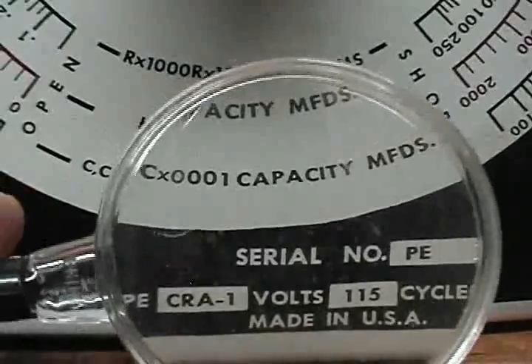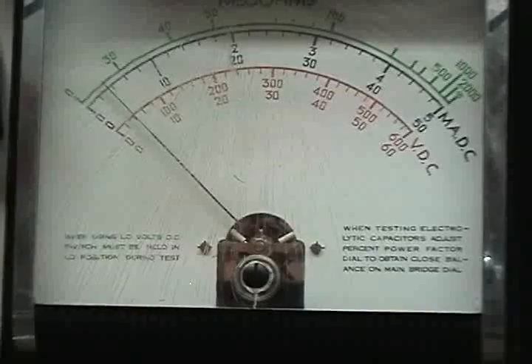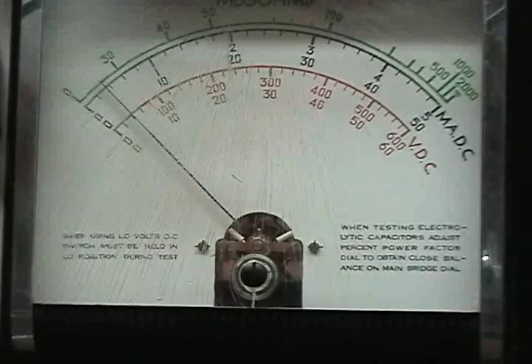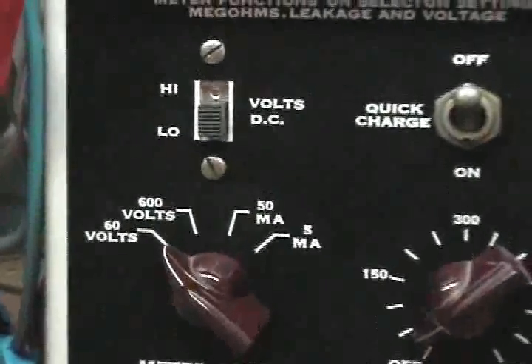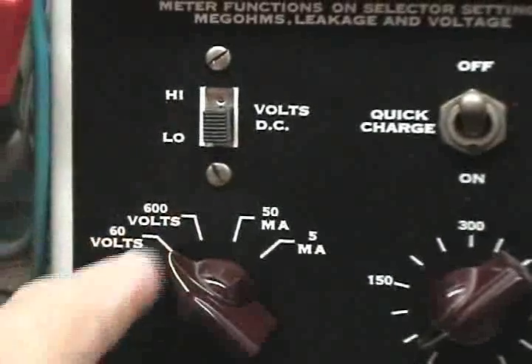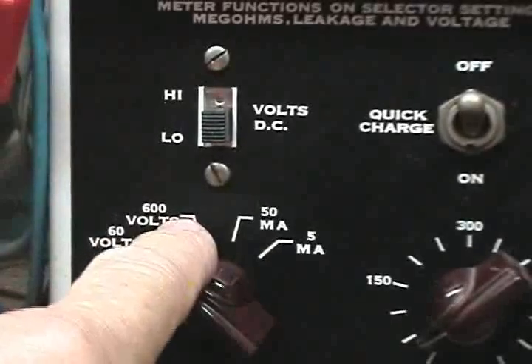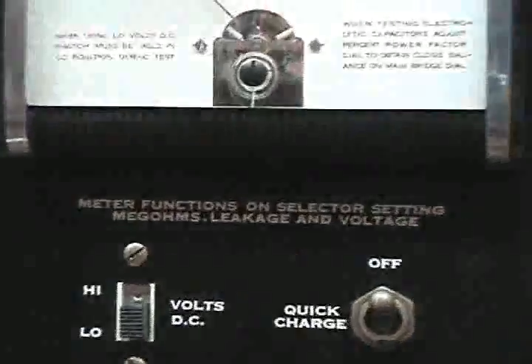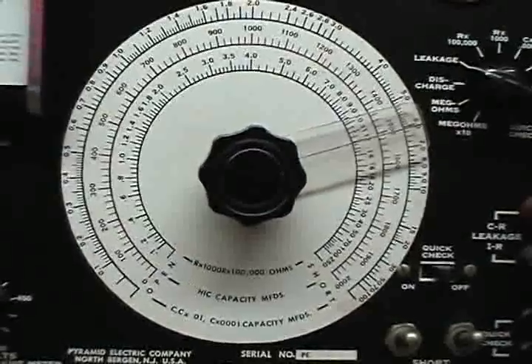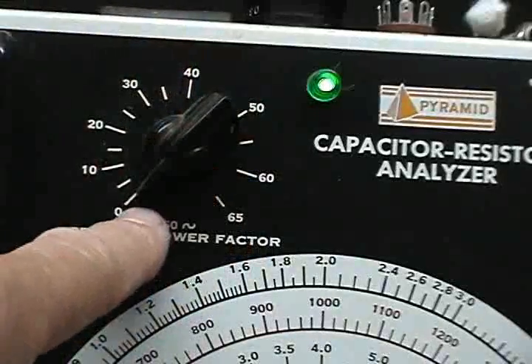This is one of the best capacitor checkers I've ever used. It has a nice meter that registers both milliamps and voltage. You get the high scale, the low scale, you got the zero to 60 volts, zero to 600 volts, and then your current over here. You got your Wheatstone bridge.